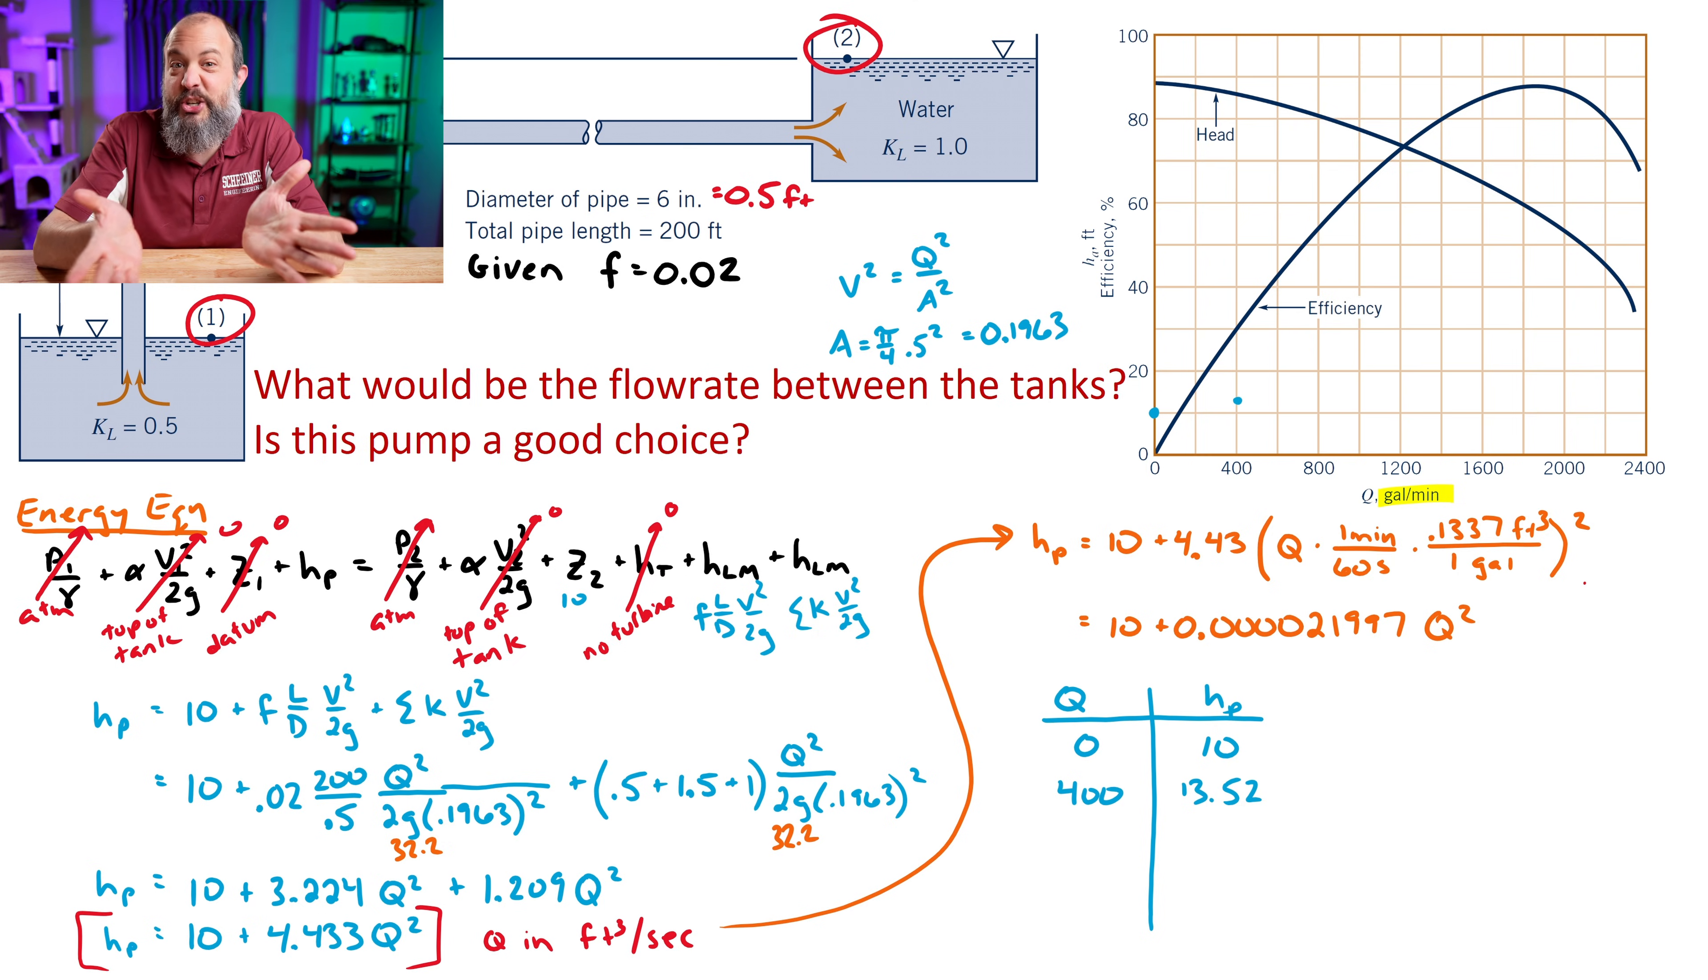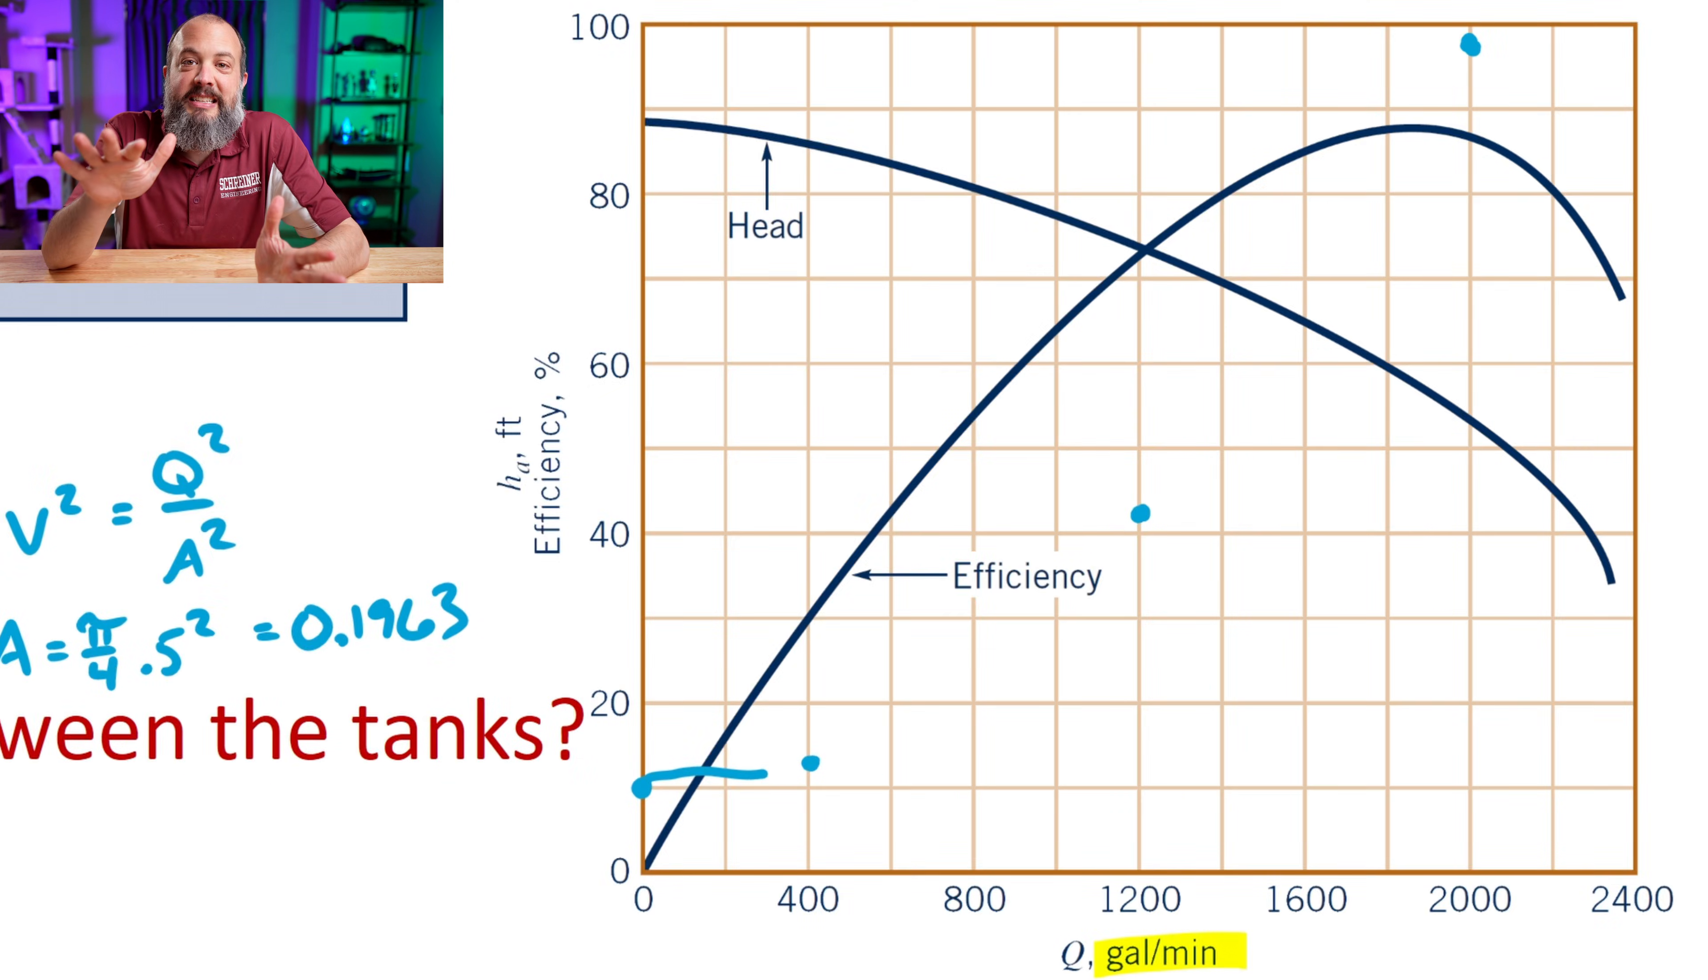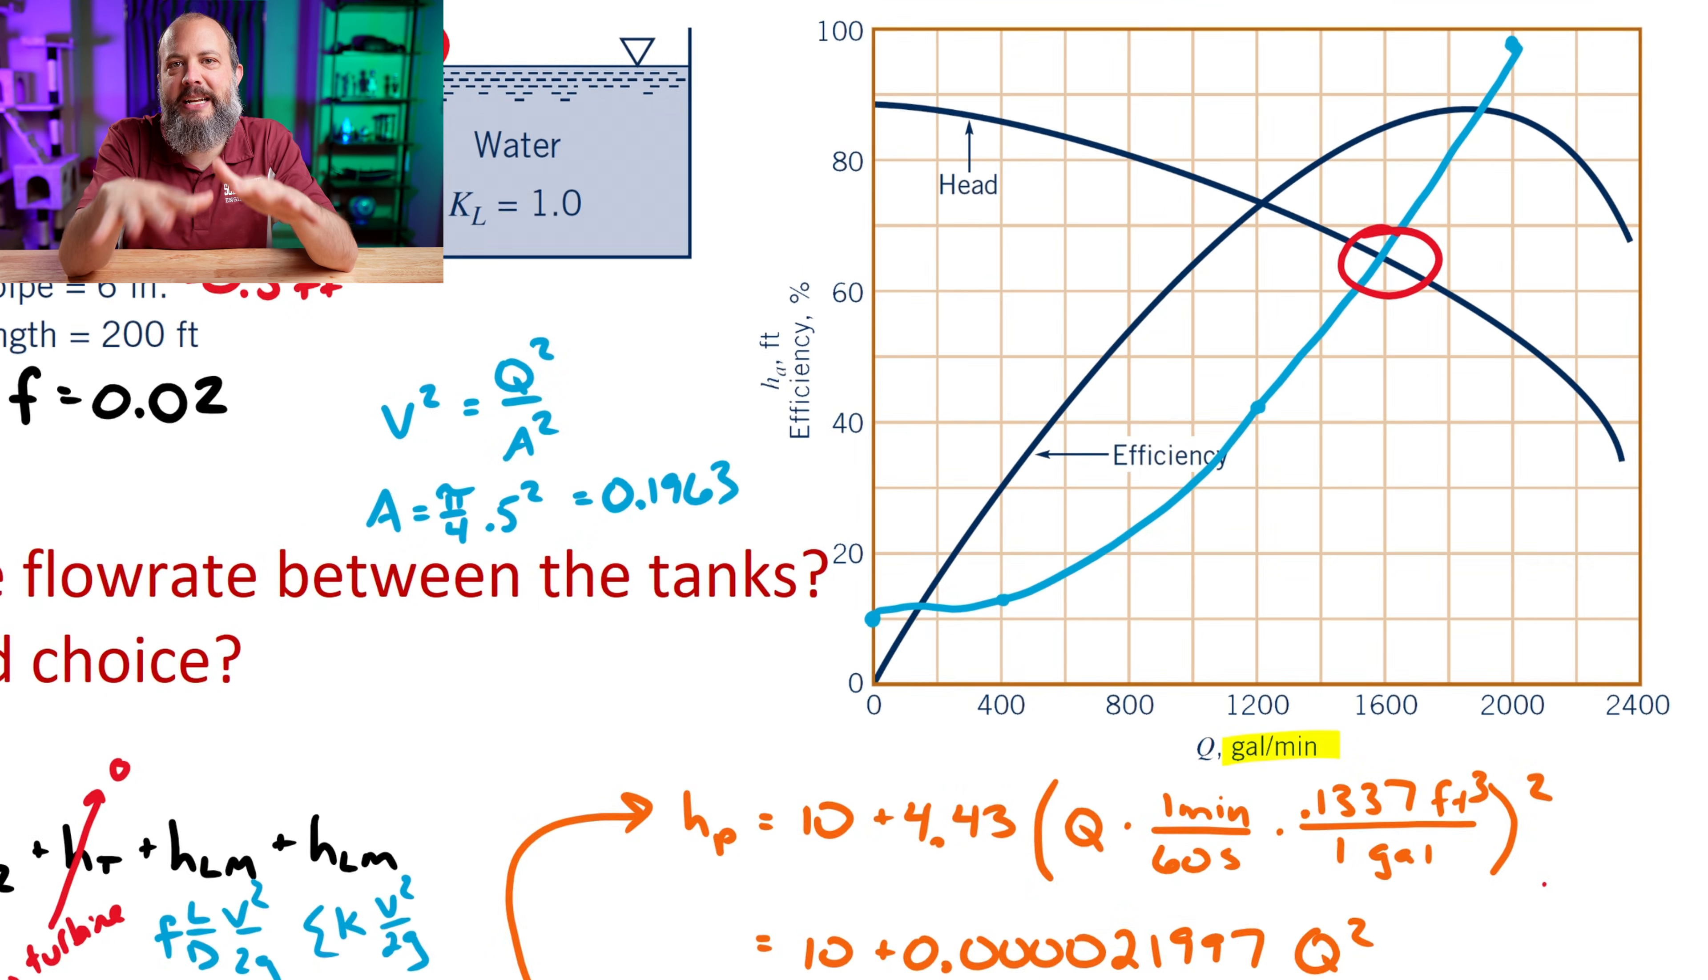Q is just going to equal 10 at a flow rate of 0. Flow rate of 400 gives us 13.52 head loss. At 1,200 gallons per minute, we've got about 41 units of head loss that the pump is going to have to provide. And at 2,000 gallons per minute, we're up around 98 feet of head loss. So as I plot that curve, it looks like our system curve intersects the pump curve right at like 1,600 gallons per minute.